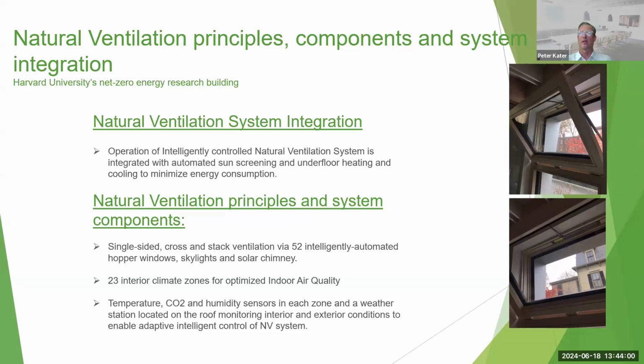These zones are created in the software which the controller uses to operate the windows. So you can have a zone which operates the windows on two opposite elevations of the building when you want cross ventilation to occur, or you can have a zone which operates the solar chimney, for example, to modulate the amount of air drawn in through the lower levels. The project has temperature, CO2, and humidity sensors in each zone, and a weather station, which is located on the roof, and that monitors the exterior conditions, including wind speed and direction, which helps to decide how much and when to open each vent location on the building envelope.